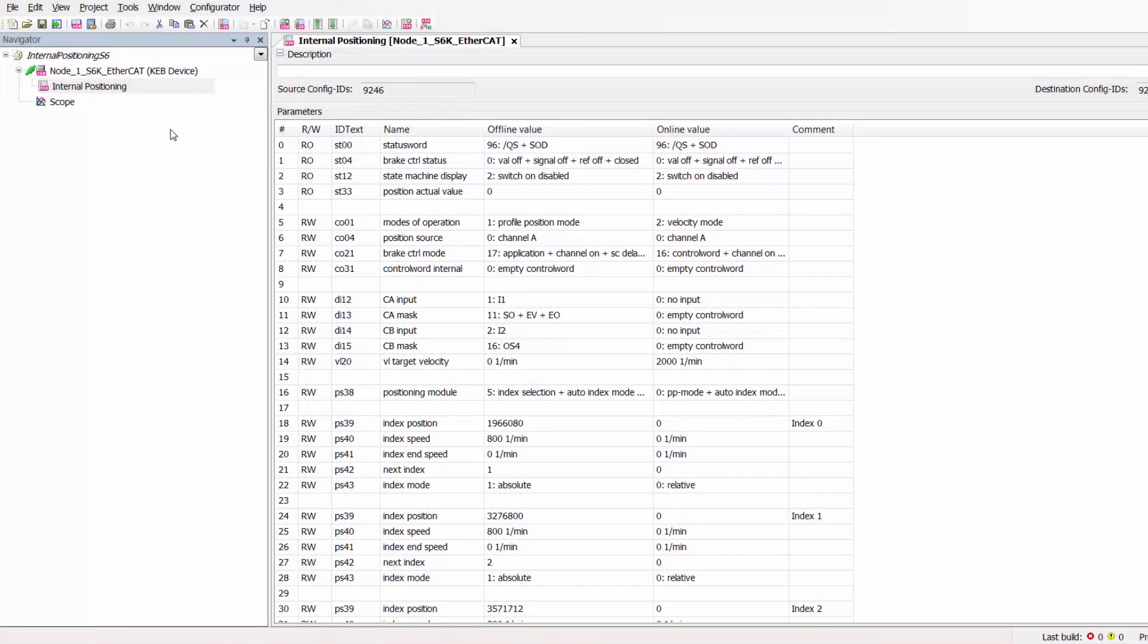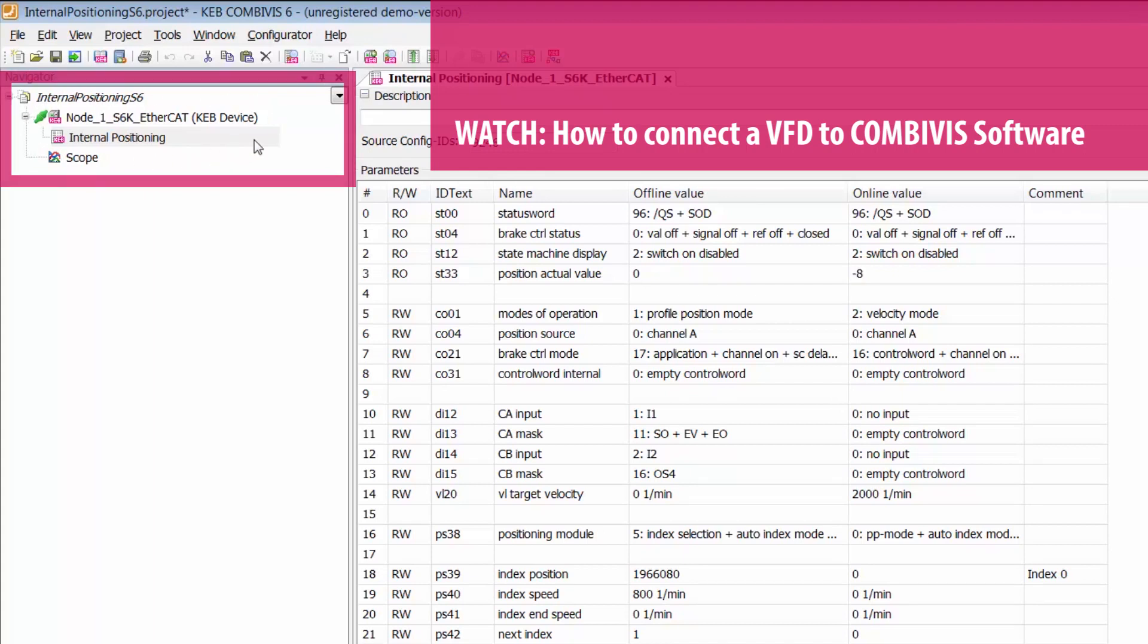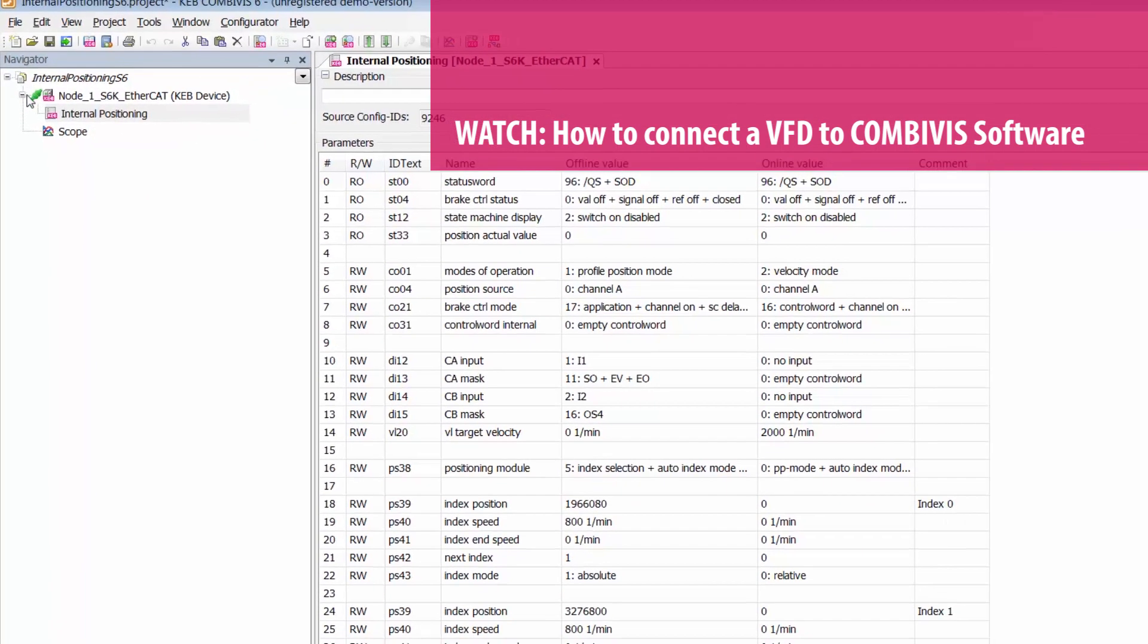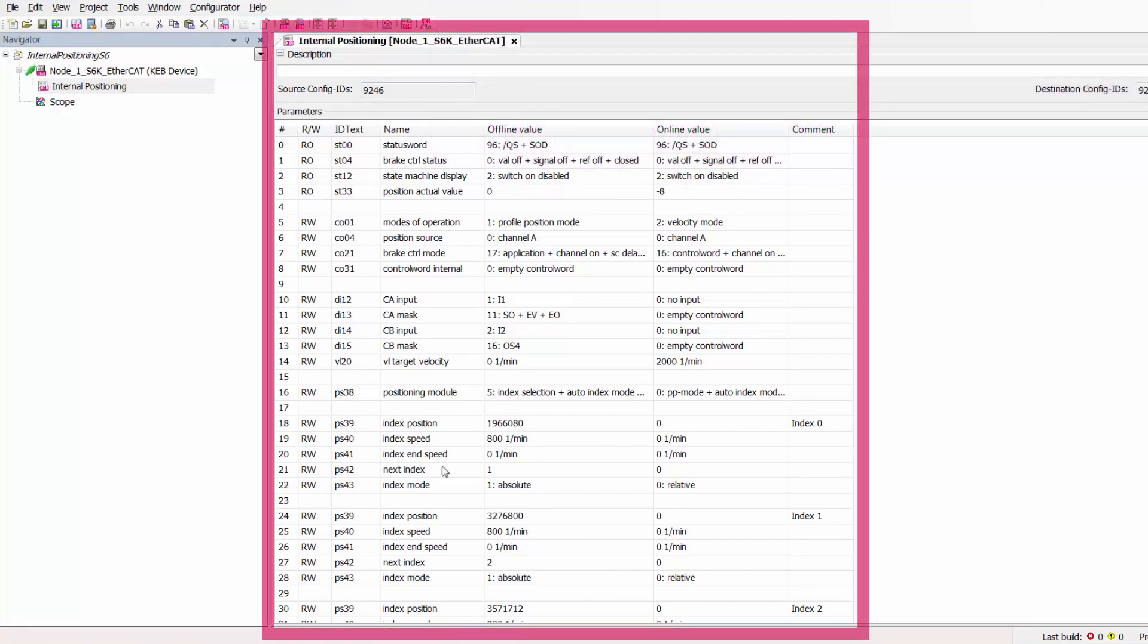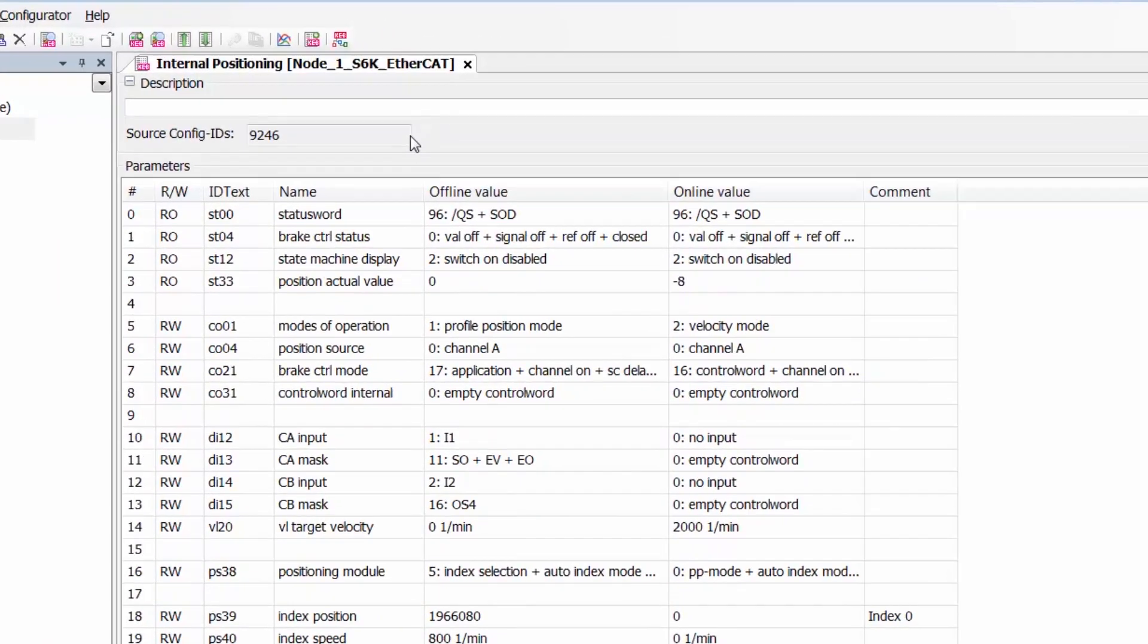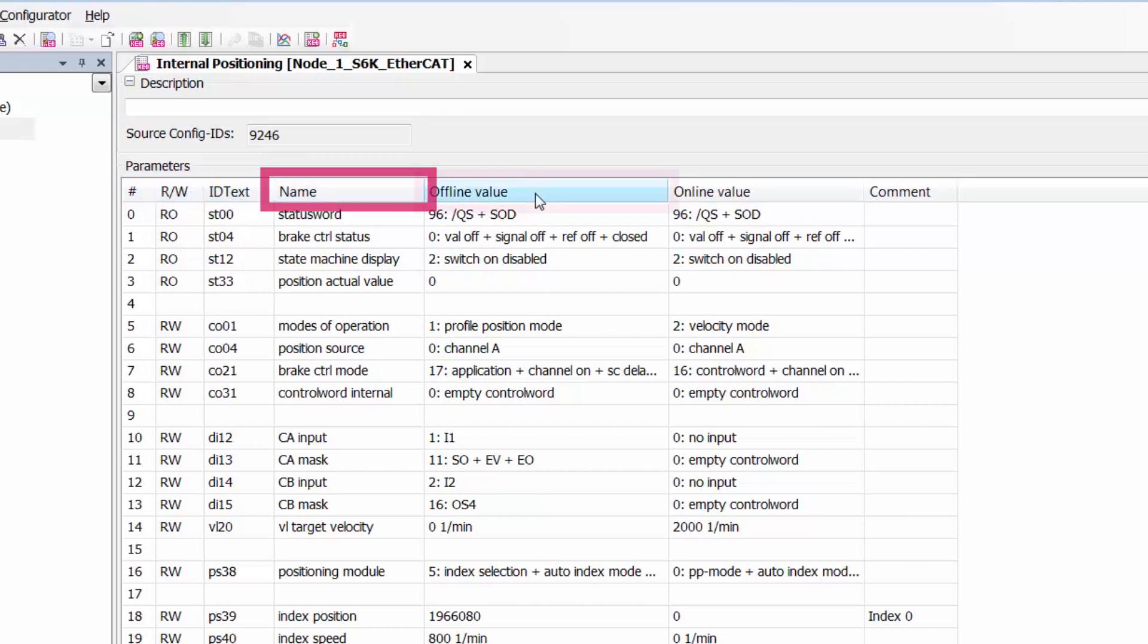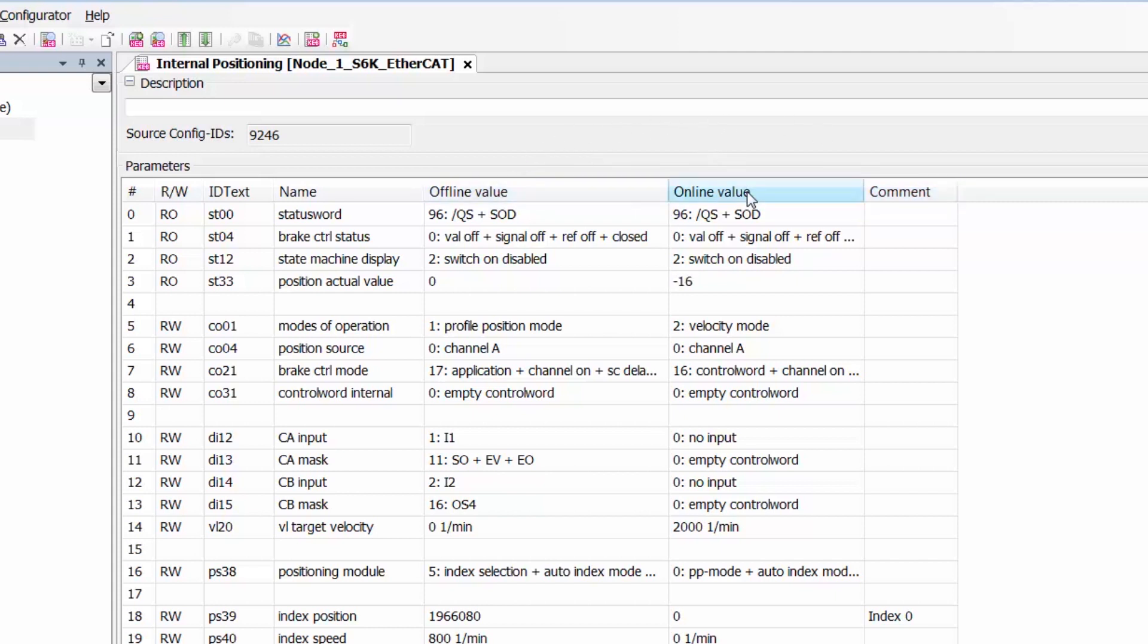So now here in CombiVis I've connected my drive and I've created this internal positioning parameter list that we're going to be using for this internal positioning module with the S6 drive. Inside this internal positioning parameter list we see a set of parameters here that I have added before the start of this video. Taking a brief look at our parameter list we have our read-write designator, our ID text, our parameter name, the offline value column which contains the user-defined values that are stored inside the parameter list, our online value column which are real-time values that are only displayed when connected to a KEB drive, and our comments section. We can write the offline value to the online value using the download list to device option that we will employ later in this video.